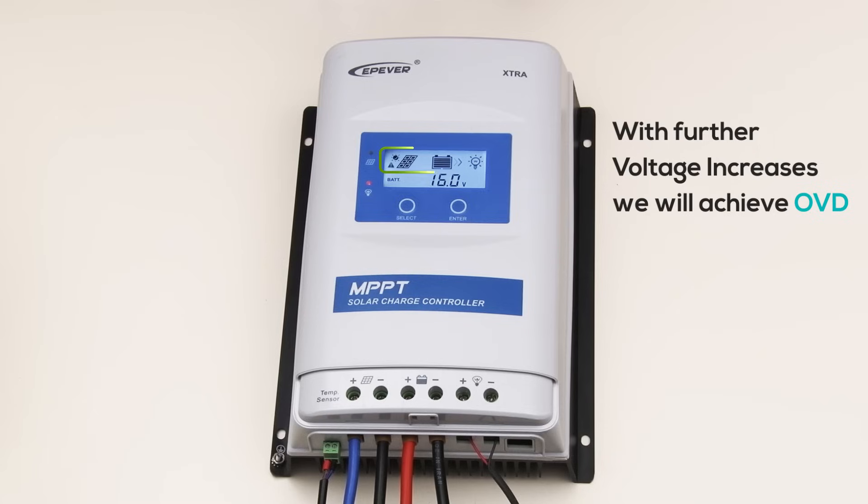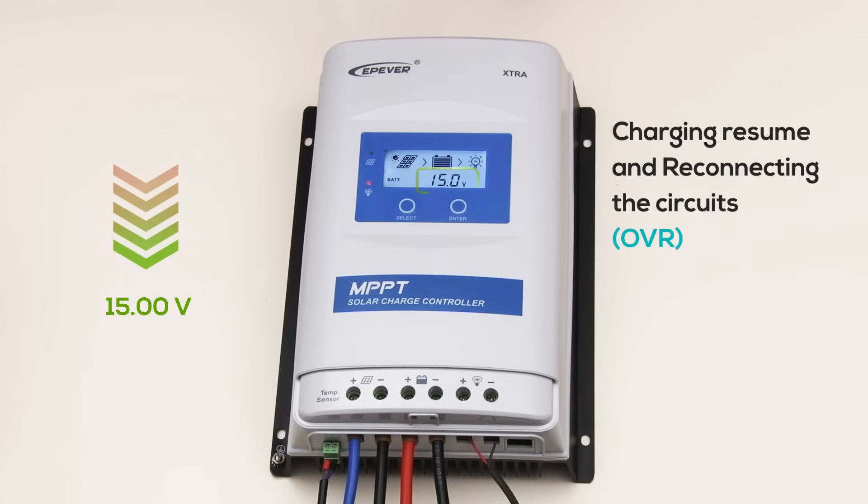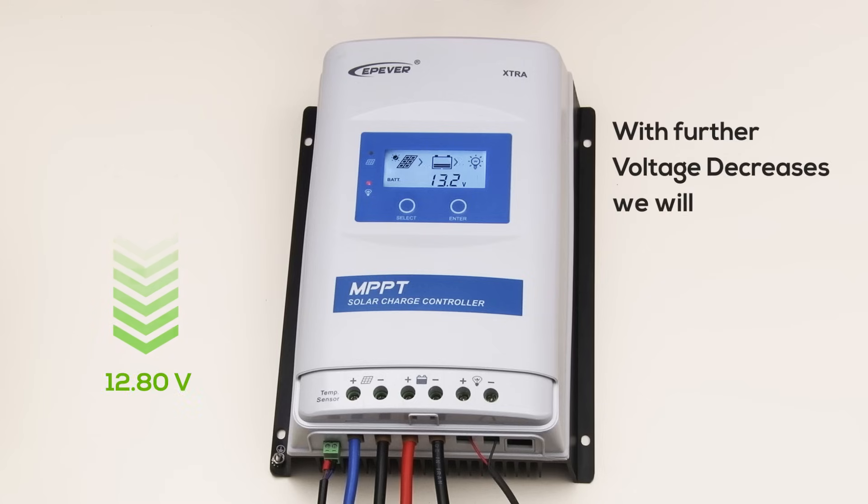It stops charging but supports loads. I'll now reduce the voltage to 15V. The controller senses this safer level and allows charging to resume, reconnecting the circuit at the OVR. Next, let's simulate a controlled discharge. As we drop below 13V, the system is ready to reinitiate LVR, ensuring the battery doesn't dip too low.